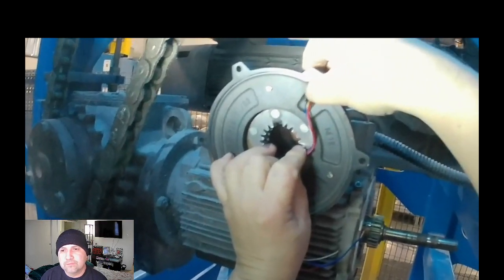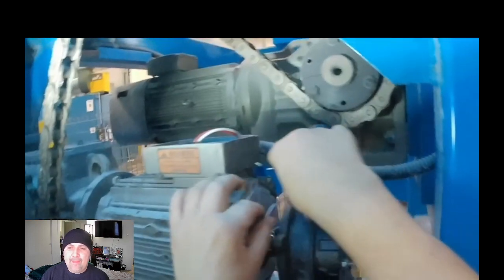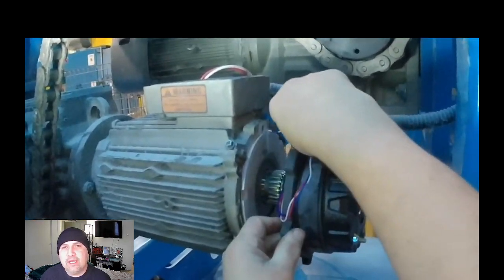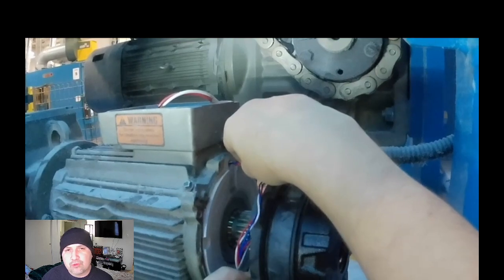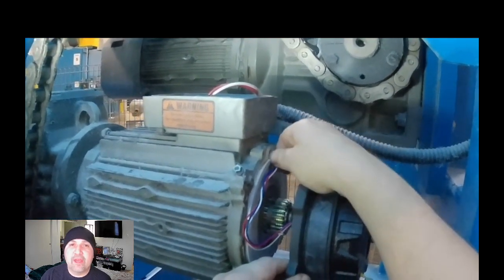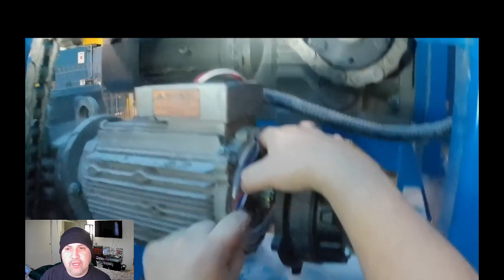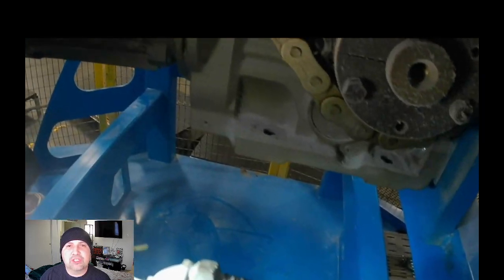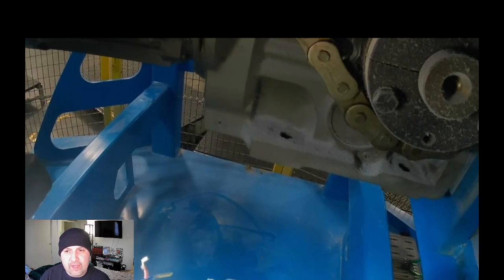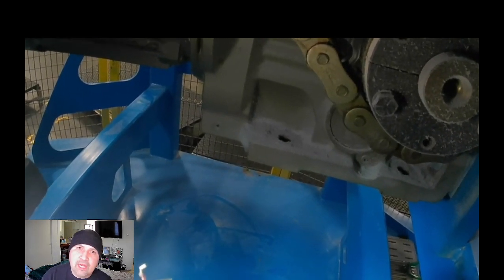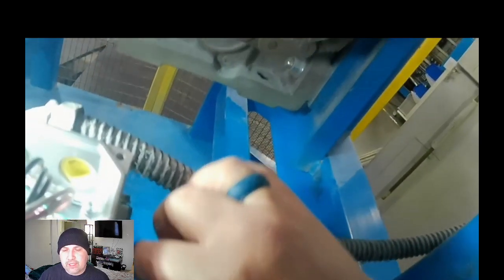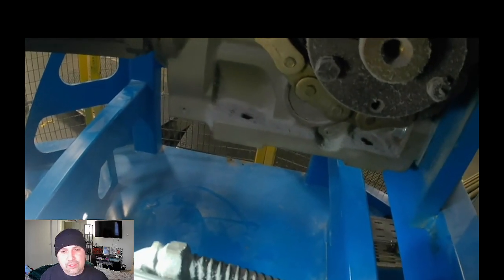Oh, they were cooking. Those wires were cooking in there. Ooh, yeah. So what ended up happening was, the brake got smoked because one of those relays had failed. So the machine was operating and the brake was just cooking in there. So the brake had failed, which took out the relay, or the relay failed, which took out the brake. So there were several things going on here, and it took me a while to troubleshoot through that. All right, there you go, and that identifies where I was with that.